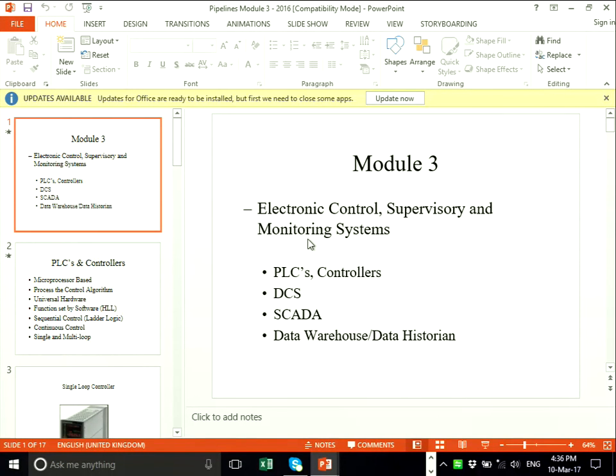So you've got to make sure you specify your system, look at the metrics on how quickly it can bring itself back up, because you might have to do it just for general software changes. Our friends at Microsoft often will issue software patches, which mean taking things down as well. Another reason for having redundancy at that central level. And usually the data links, the telemetry links, are typically duplicated. So I mentioned satellite, but typically you'll have maybe satellite and say an ISDN line. So if you can't get it on that, you get it on that. So you try and minimise the chances.